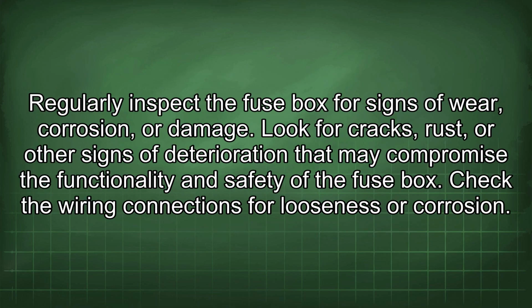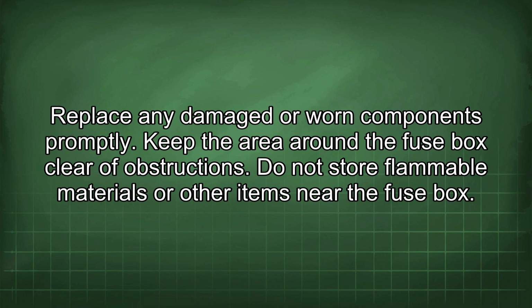Regularly inspect the fuse box for signs of wear, corrosion, or damage. Look for cracks, rust, or other signs of deterioration that may compromise the functionality and safety of the fuse box. Check the wiring connections for looseness or corrosion. Replace any damaged or worn components promptly.